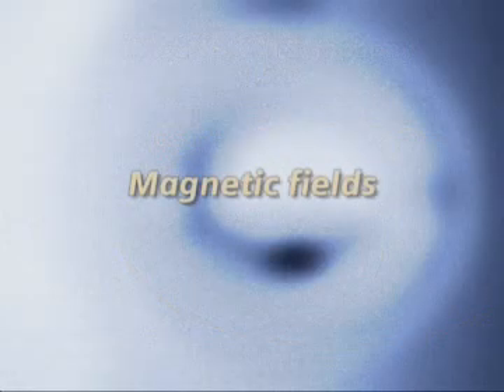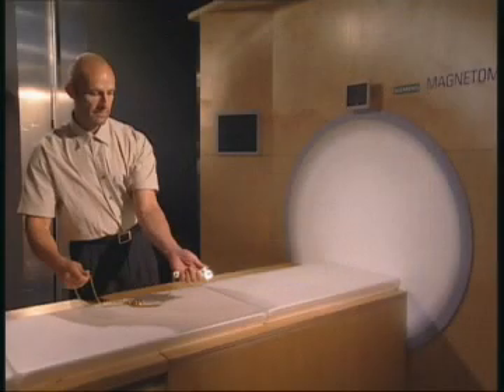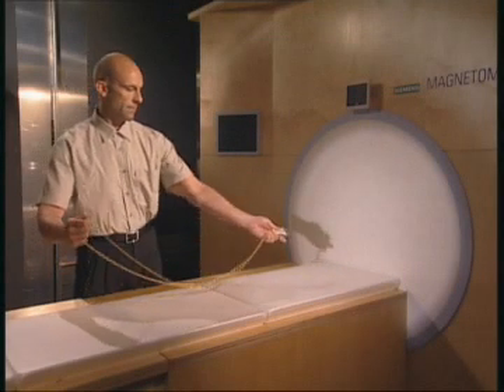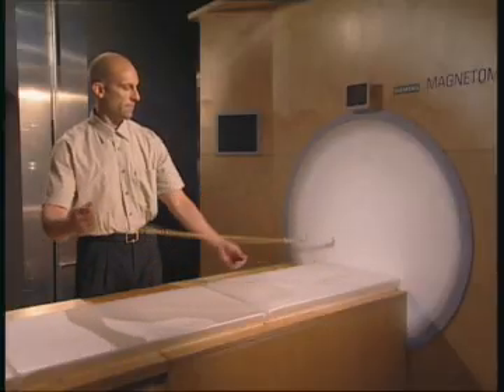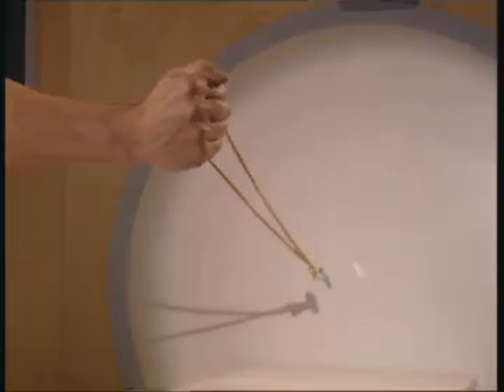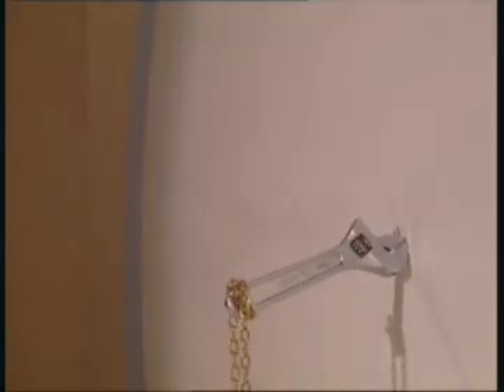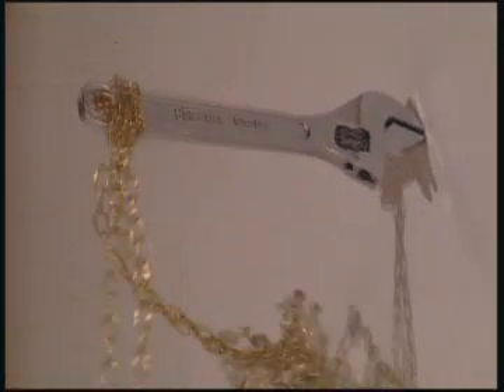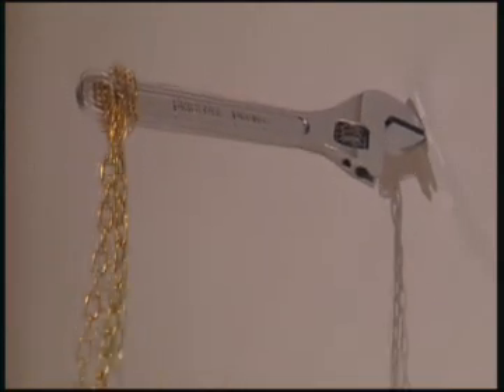Magnetic fields. The force exerted by an MR magnet on a magnetizable object depends on the degree to which the magnetic field changes spatially. This spatial change can be quite abrupt for shielded high-field magnets. The attractive force is powerful and arises suddenly.